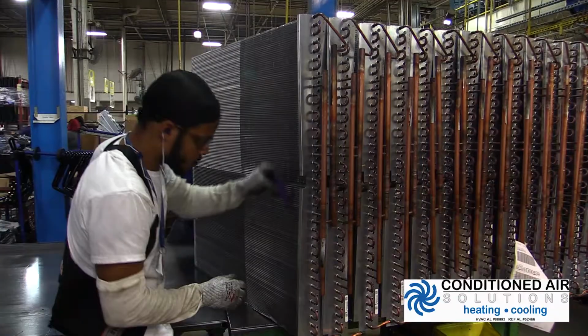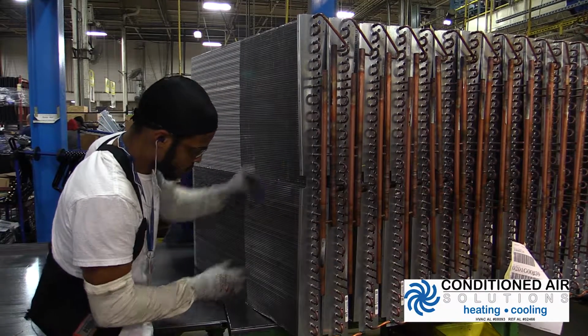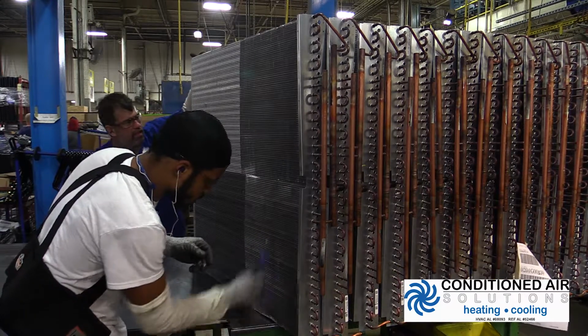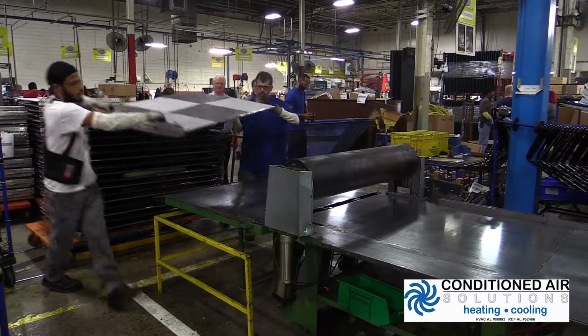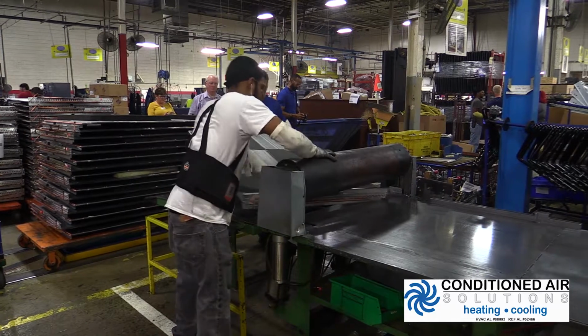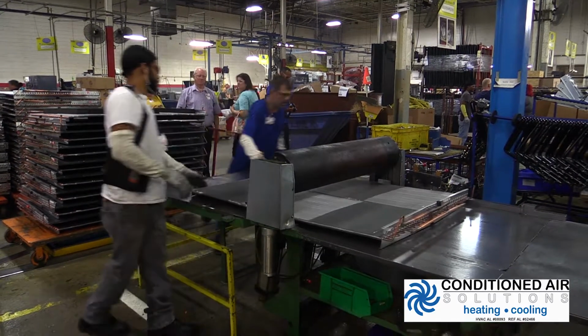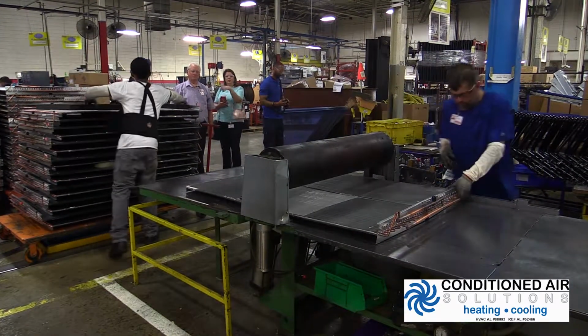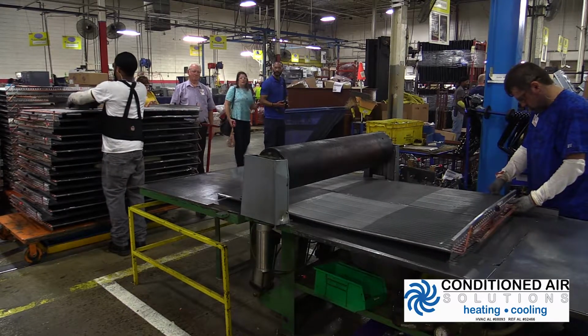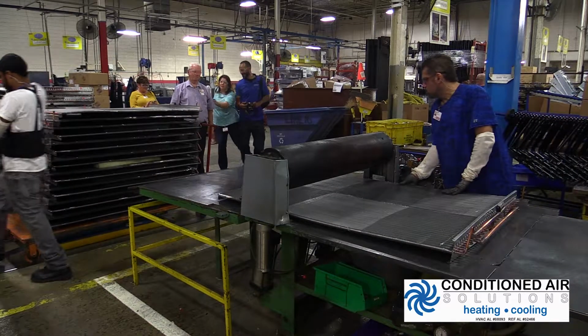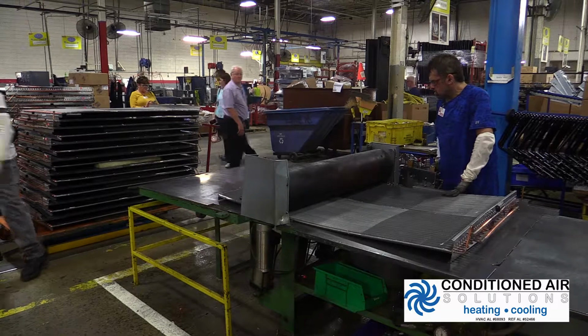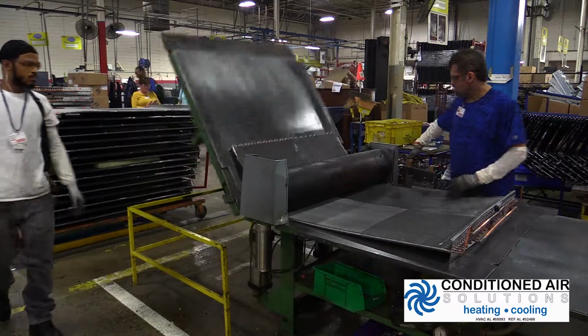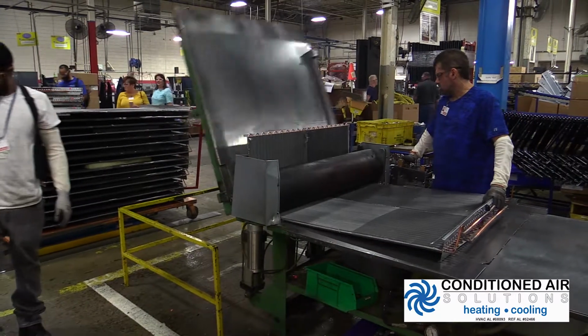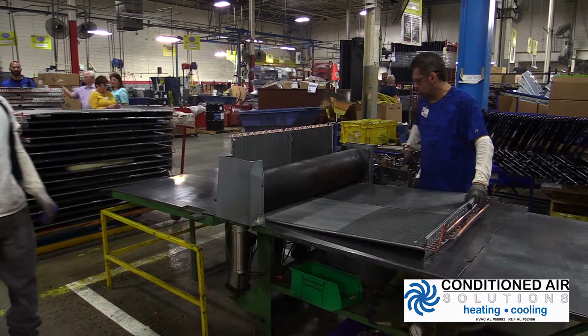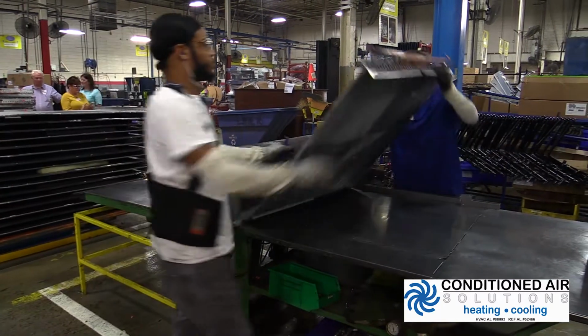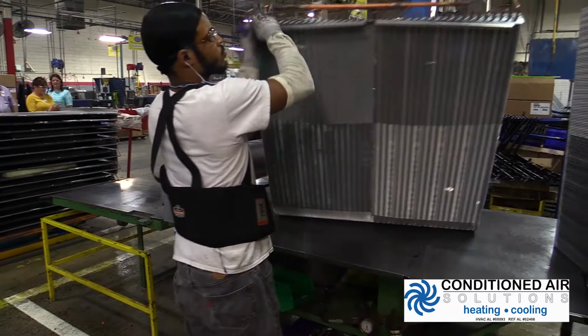The cooling coil for the outdoor unit dissipates the heat captured by the indoor coil as it cools your home. This coil is large and must be shaped to provide maximum space in the unit. This heat transfer surface is made with aluminum fins and copper tubing. The forming of the outdoor coil requires special care not to distort the fins and protect inside of the copper tubes. The special tools and well-trained technicians form the coil and install it in the base of the unit as it moves on the assembly line.